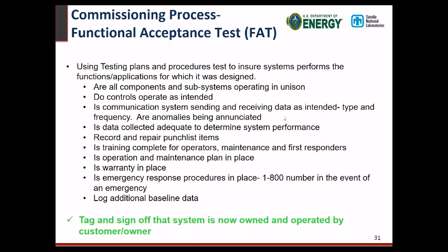Does it go to an idle state? Is it safe? Does not have any problems? If it does, you need to have them fixed. You want to make sure that all your alarms went off. So when the power went off, did you receive like a system alarm saying that AC voltage was lost? So you want to make sure that you are getting the faults and stuff that you're supposed to be getting.